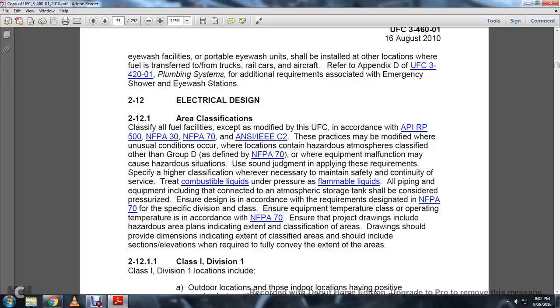The practice is modified where unusual conditions occur, with locations containing hazardous atmospheres classified other than Group D as defined in NFPA 70, where equipment malfunction can cause a hazardous situation, and use sound judgment in applying the requirements, specifying the higher classification when necessary to maintain safety and continuity in service. Treat combustible liquids under pressure as flammable liquids. All piping and equipment connected to the atmospheric storage tank shall be considered as pressurized.